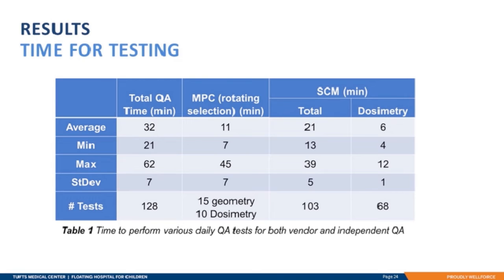As was mentioned earlier, during this period, we did have some reliability issues with Machine Performance Check, and this is reflected in the standard deviation for Machine Performance Check being larger than SunCHECK Machine. The consistency we saw with the time to do the dosimetry checks with SunCHECK Machine was quite impressive, and the variability of the overall QA time with SunCHECK Machine is explainable with the fact there was a lot more human interaction needed with the non-dosimetry checks.